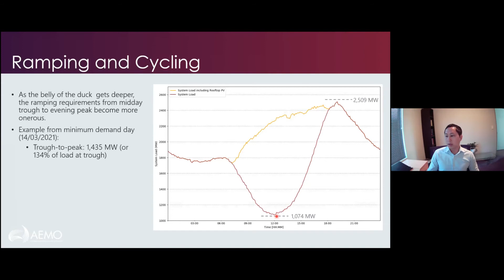But this is just for illustrative purposes from the minimum demand day, where we had quite a big duck belly. The ramp from trough to peak was about 1.4 gigawatts, so about 134% of the load at the trough, and the ramp rate was about 4 megs per minute. If we didn't have DER, excluding rooftop PV, this is the underlying load, then the ramp rate would have been 1.2 megs per minute, which would have been much more consistent with our normal summer loading.